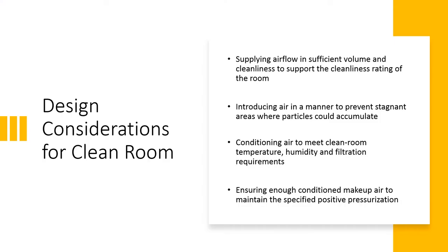There are four important air conditioning design considerations for clean room system design. First, supplying airflow in sufficient volume and cleanliness to support the cleanliness rating of the room. Second, introducing air in a manner to prevent stagnant areas where particles could accumulate. Third, conditioning air to meet clean room temperature, humidity, and filtration requirements. And fourth, ensuring enough conditioned makeup air to maintain the specified positive pressurization.